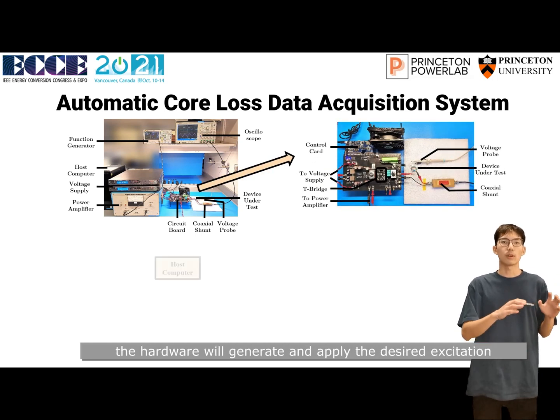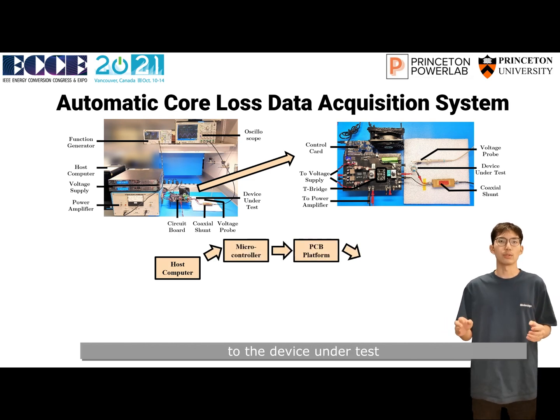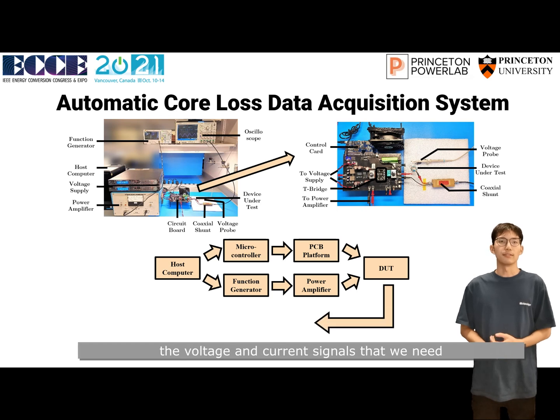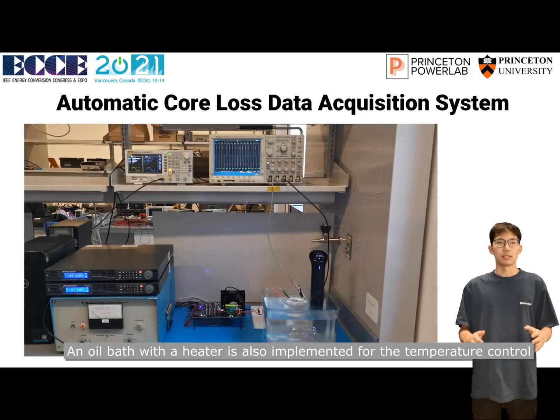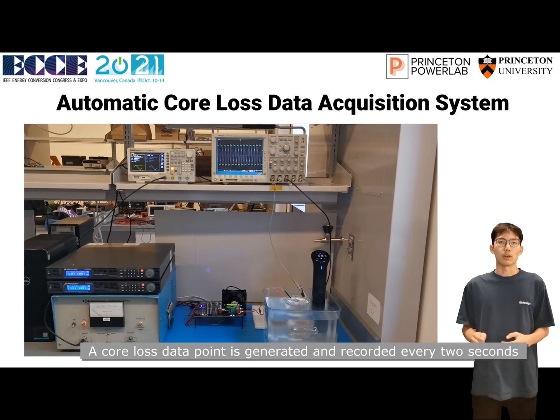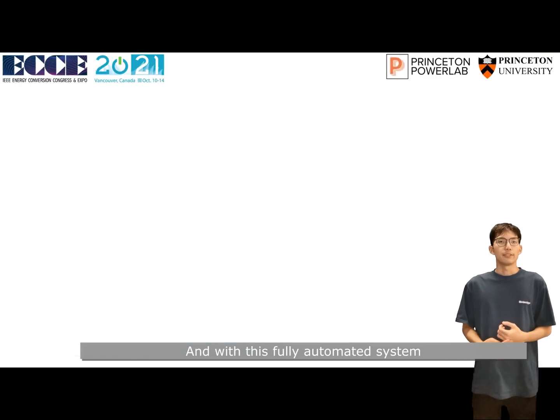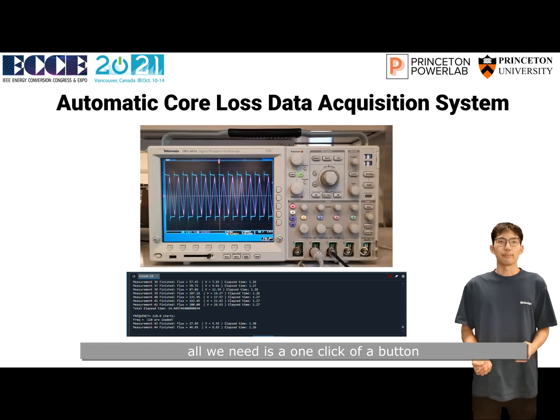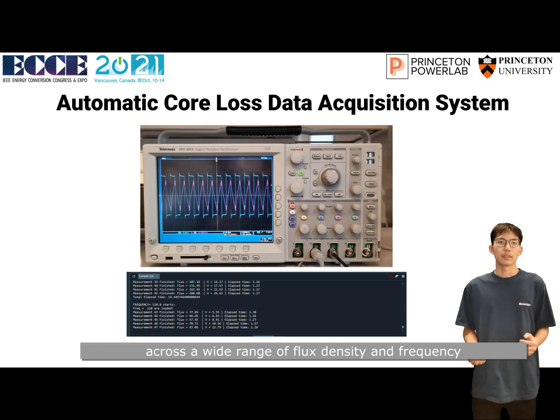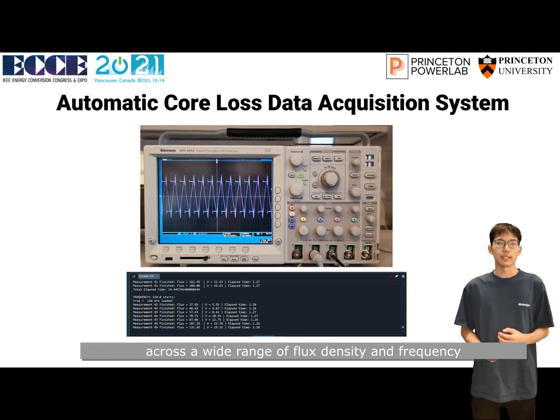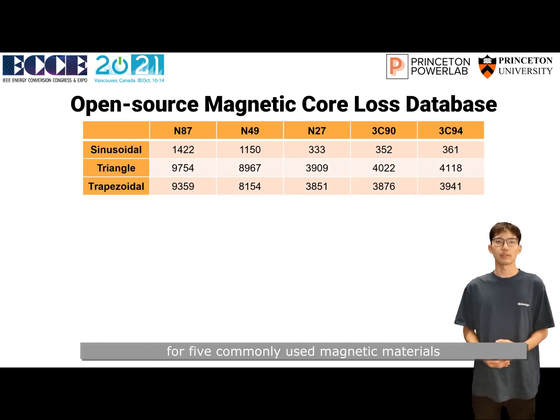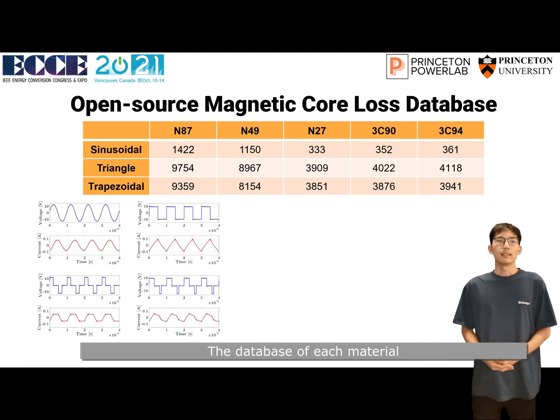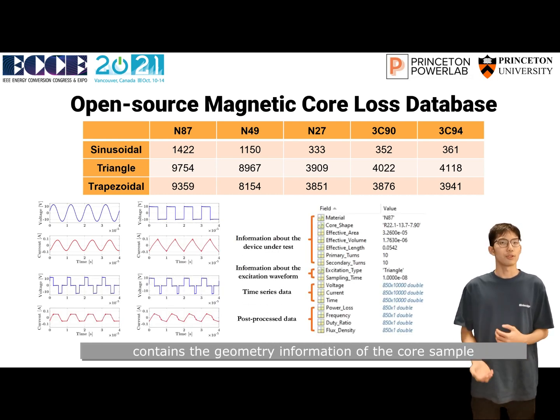With the control of the host computer, the hardware will generate and apply the desired excitation to the device under test. The oscilloscope will measure and collect the voltage and current signals that we need. An oil bath with a heater is also implemented for temperature control. A core loss data point is generated and recorded every 2 seconds. With this fully automated system, all we need is just a click of a button, and thousands of data points will be acquired in a few hours, across a wide range of flux density and frequency. So far, we have collected over 60,000 core loss data points for 5 commonly used magnetic materials with multiple types of waveforms.